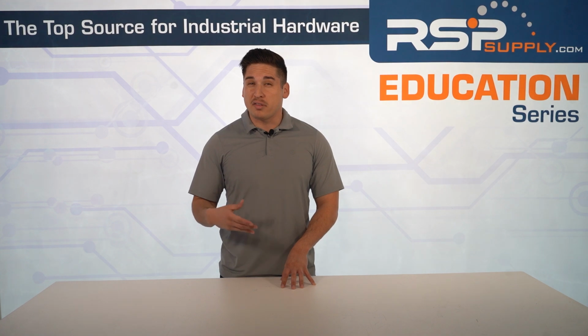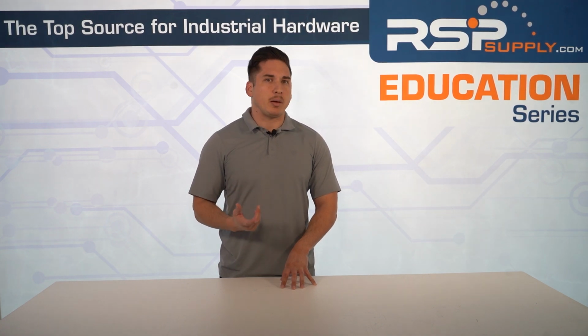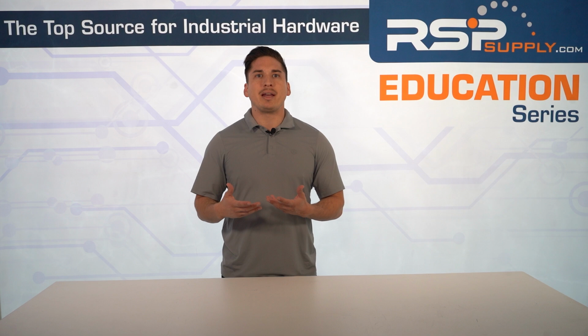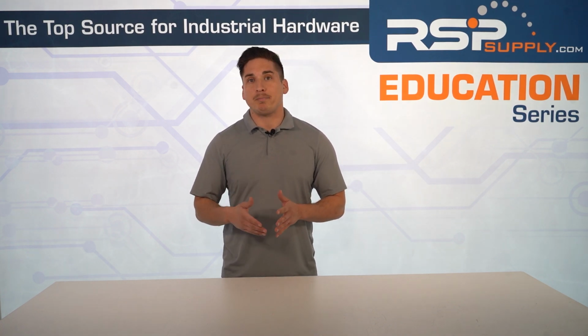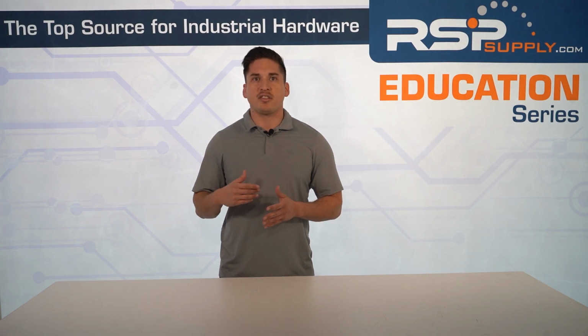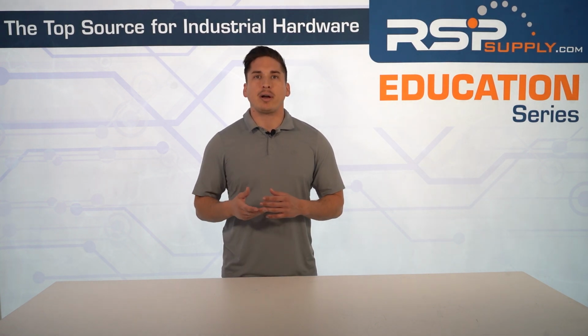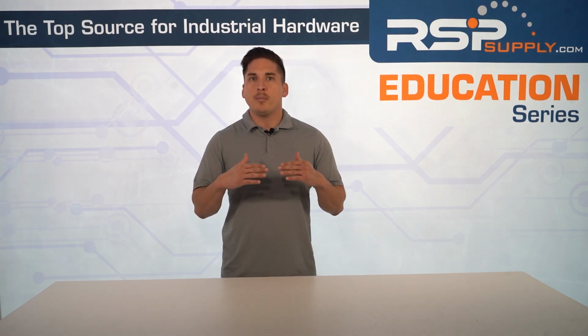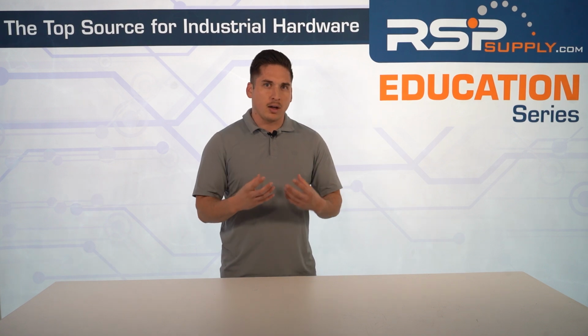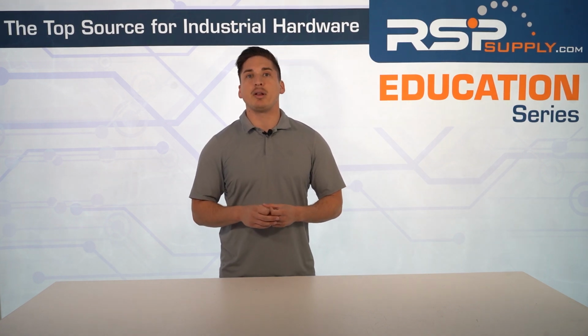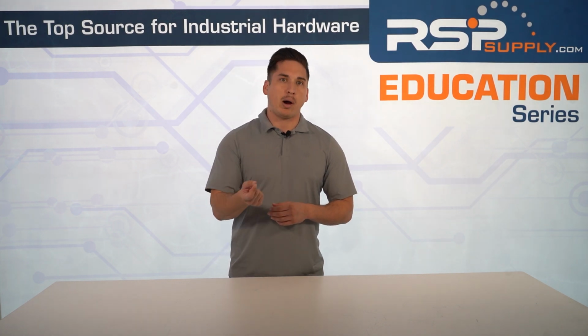Now, switchgear is also categorized by arc interrupting medium. An arc interrupting medium is a material or method used to extinguish the electrical arc that forms when a circuit breaker or switchgear opens to interrupt the flow of the current. The arc is a plasma discharge caused by the high energy of the electric current attempting to maintain continuity between the separated contacts. So efficiently quenching this arc is critical for preventing equipment damage, maintaining operational safety, and ensuring reliable operation of the power system.